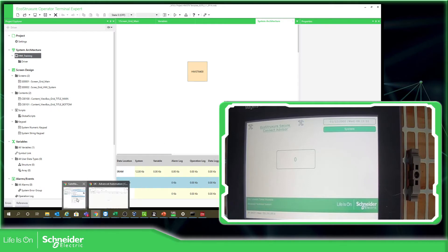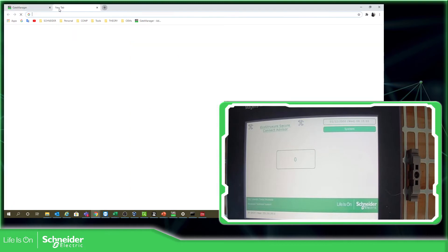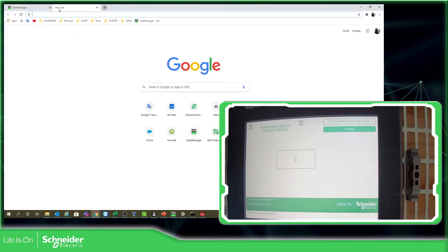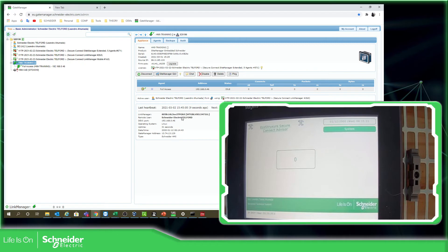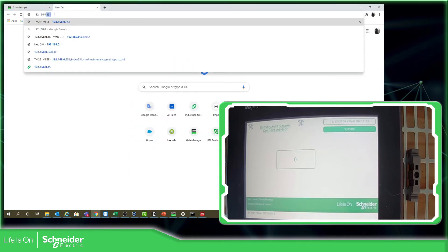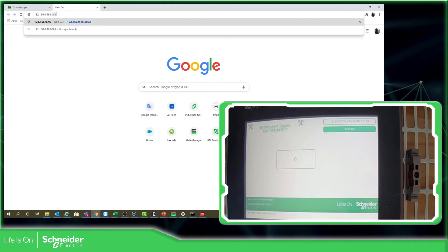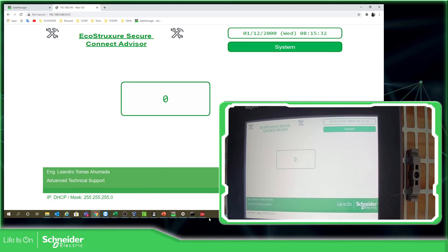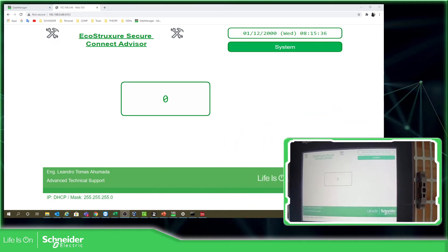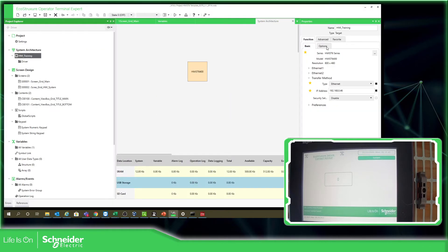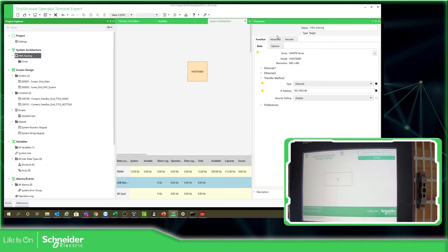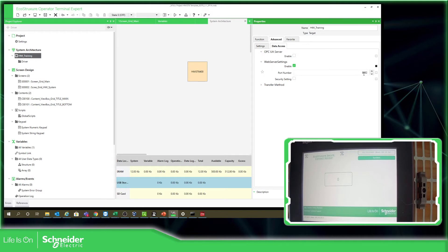Now let's see what happened — if I can access the application, the web server. The IP address is 192.168.46.x port 8082. As you can see here, we have complete access to the HMI. This number 8082 can be found here — it's what we have configured in the past under Advanced Data Access — 8082.